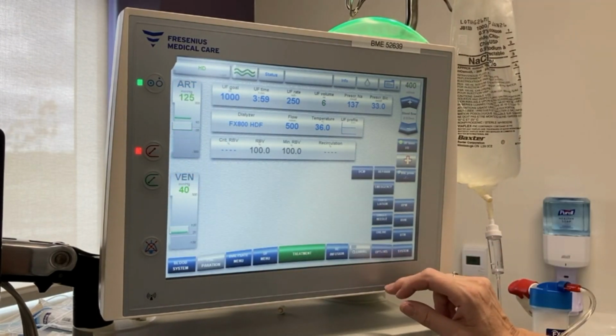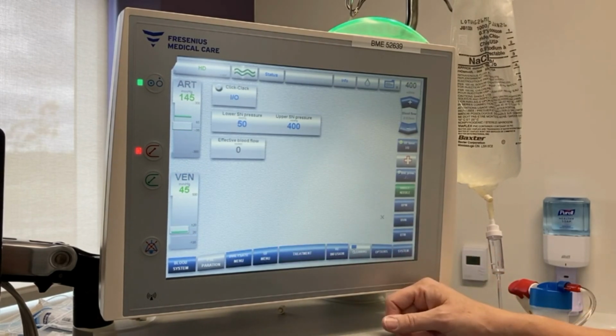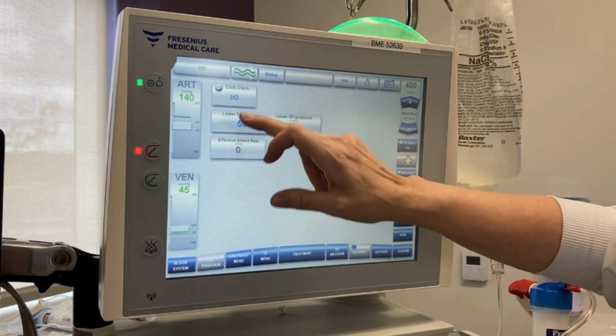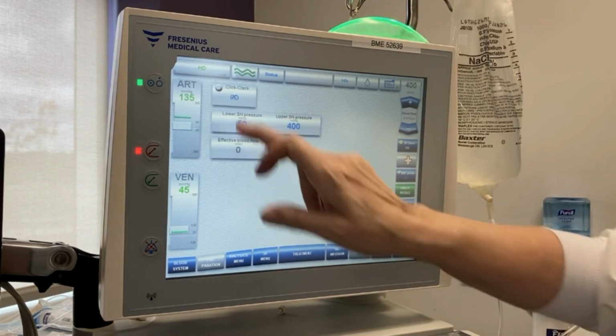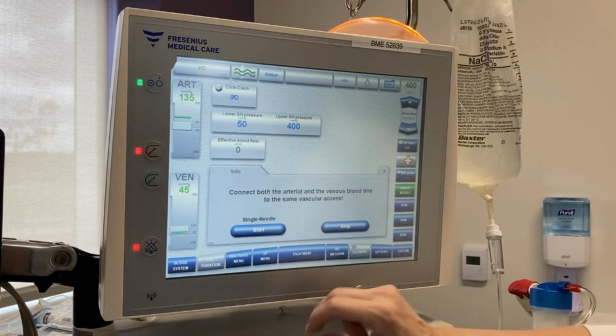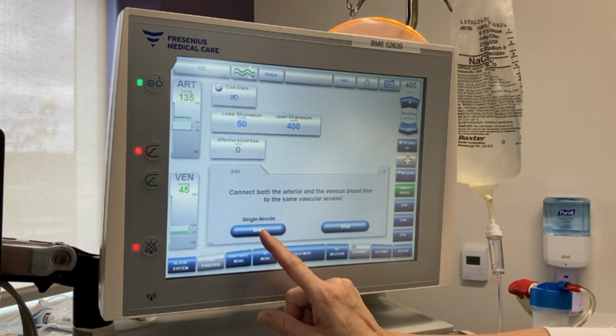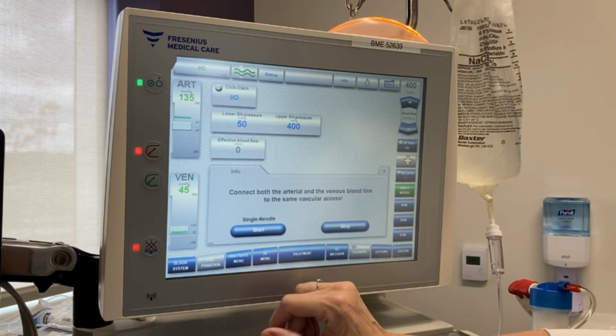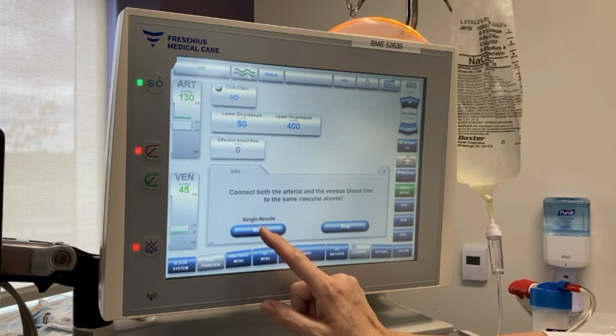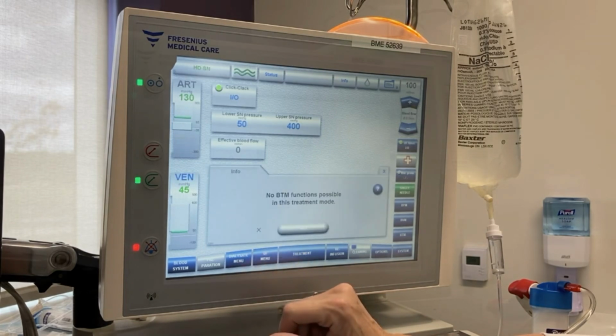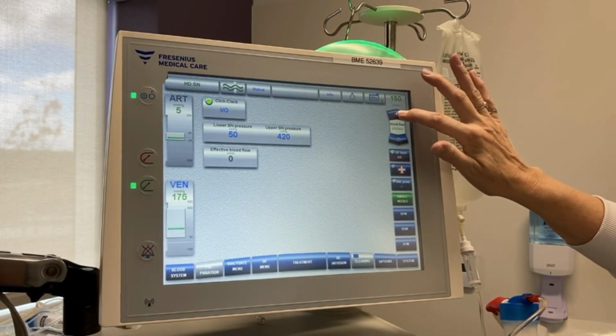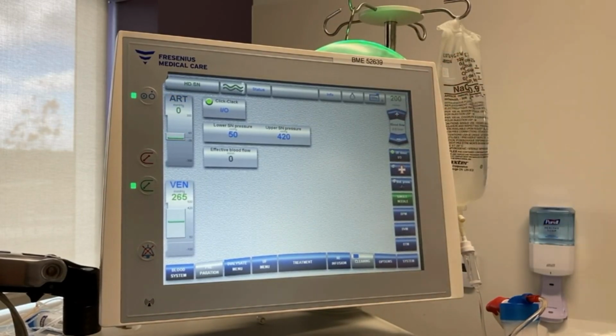So we go into the options, go to single needle, and it actually gives us the only option of click-clack. There's no single needle option, it's just click-clack. So now it says you've connected both arterial and venous bloodline to the same vascular access, which we've done using the Y connector. And so we're just going to start. So again, in click-clack, we just want to increase the pump speed. We don't want to increase it as much. We can't increase it as much as when we're using the 2 pumps.